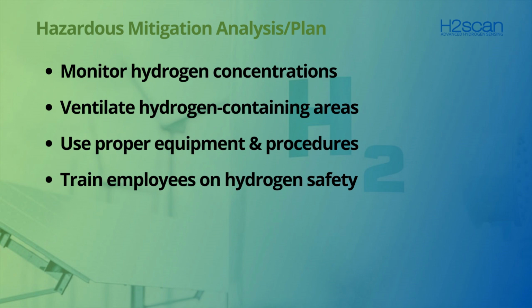And as we discussed, there are a variety of different sensors to help us do this. And of course, depending on your application, you have to do a detailed analysis on which sensor actually meets your requirements. Second, we have to provide proper ventilation to hydrogen-containing areas. Adequate ventilation is essential for preventing accumulation of gas. Hydrogen gas is lighter than air, so it will rise to a ceiling if it's indoors. And as a result, ventilation systems should be designed to extract hydrogen gas from the upper part of the room. And of course, hydrogen monitoring and ventilation can work together, where the monitor can trigger the ventilation system to turn on when an unsafe level of hydrogen is detected.